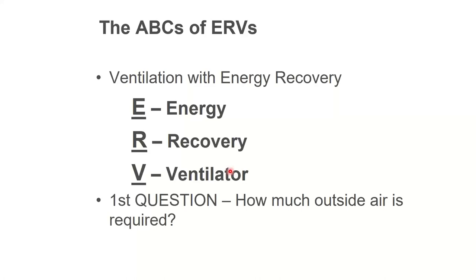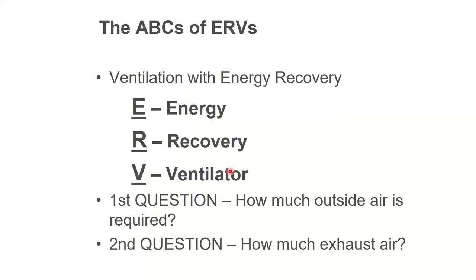And the reason is, for an ERV, generally speaking, all the control widgets and the labor to install it and all that stuff is pretty fixed for the size, right? But the more CFM I have, the more energy I can recover. So having an ERV that's doing 2,000 CFM versus one that's 200 CFM, it gets more interesting on a per CFM basis, financially speaking. So lots of outside air is the target for this kind of stuff.